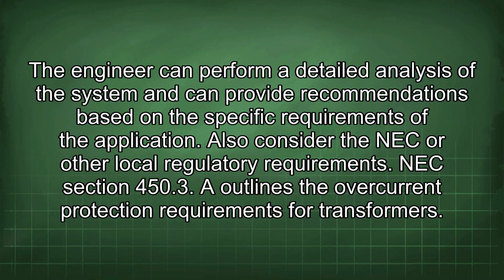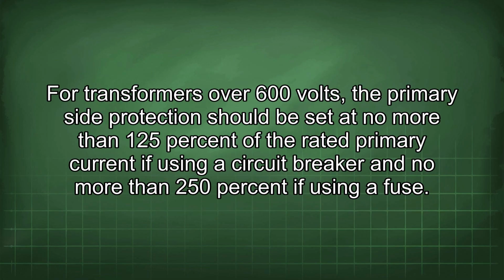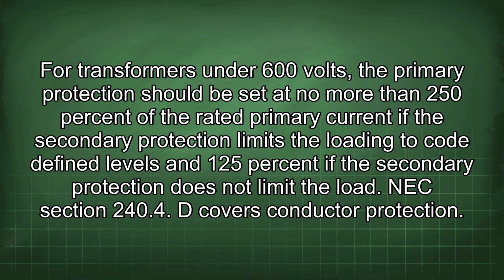NEC Section 450.3 outlines the overcurrent protection requirements for transformers. For transformers over 600 volts, the primary side protection should be set at no more than 125% of the rated primary current if using a circuit breaker and no more than 250% if using a fuse. For transformers under 600 volts, the primary protection should be set at no more than 250% of the rated primary current if the secondary protection limits the loading to code-defined levels and 125% if the secondary protection does not limit the load. NEC Section 240.4(D) covers conductor protection.